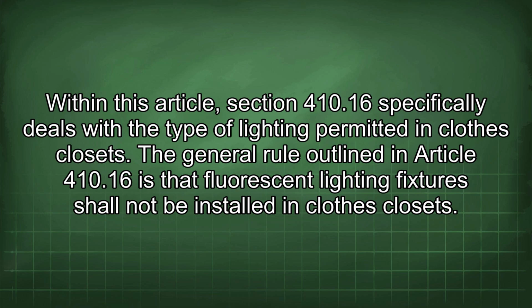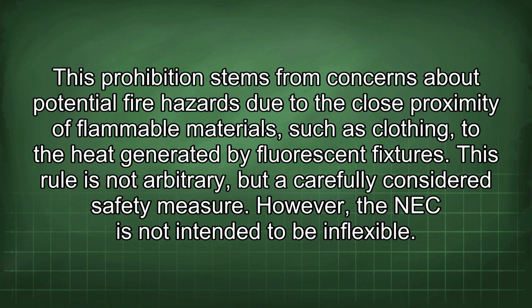The general rule outlined in Article 410.16 is that fluorescent lighting fixtures shall not be installed in clothes closets. This prohibition stems from concerns about potential fire hazards due to the close proximity of flammable materials such as clothing to the heat generated by fluorescent fixtures. This rule is not arbitrary but a carefully considered safety measure. However, the NEC is not intended to be inflexible.